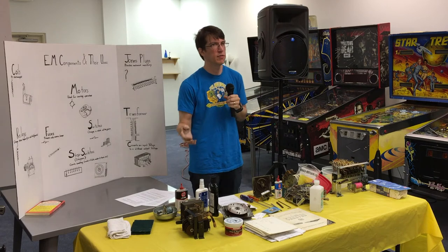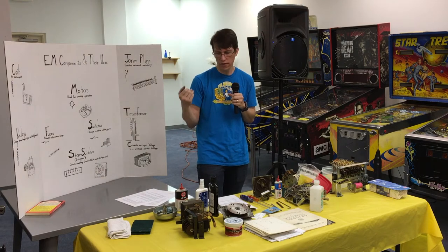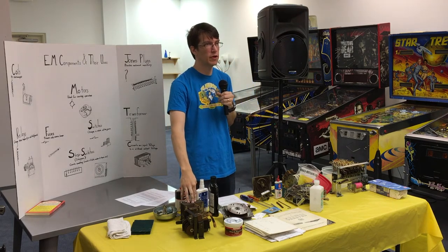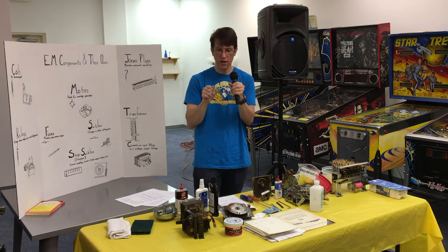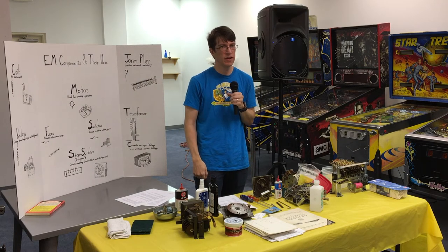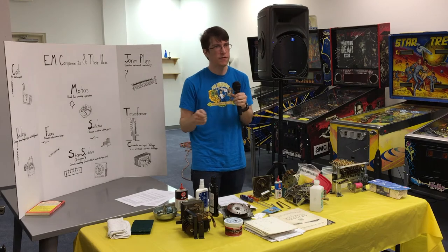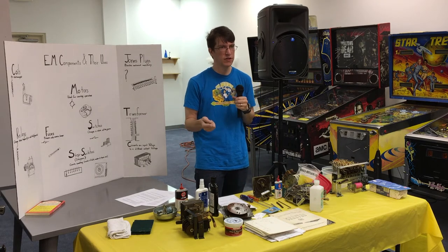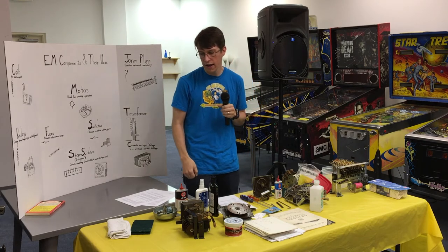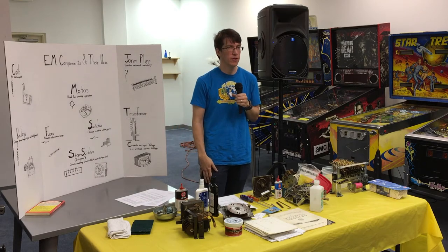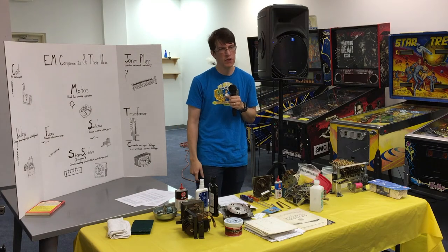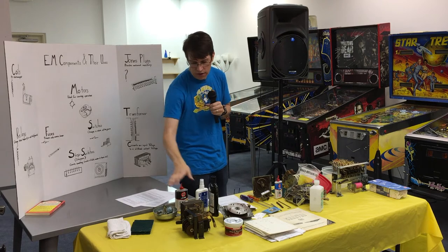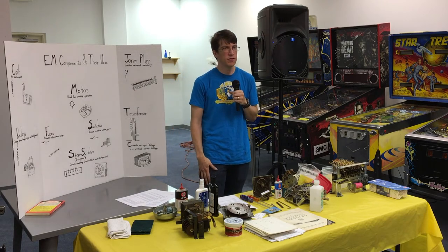There's going to be a fuse that protects your line voltage. It actually protects the transformer. It's called your primary fuse. You can see if you've got 110 volts across that fuse. There's going to be a 50 volt or 24 volt fuse that protects your coils. Check that. Then you're going to have a 6 volt fuse or fuses that protect your lamps. Check across that. Don't bother messing with the transformer unless you absolutely have to.